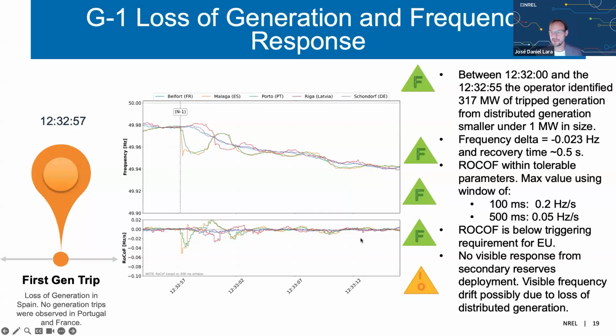And you can see here from the RoCoF, the rate of change of frequency, that at no moment was the rate of change of frequency even close to triggering rate of change of frequency protections in the system. And one of the things that we observe in this plot for the first seconds after the trip is that we don't observe any visible response from the reserves. There's no data in the report so far to explain this downward behavior of the frequency, despite the fact that, again, if you look at the rate of change of the frequency itself, the protections for frequency are not within the range that could have actually triggered a trip of more units due to frequency changes.